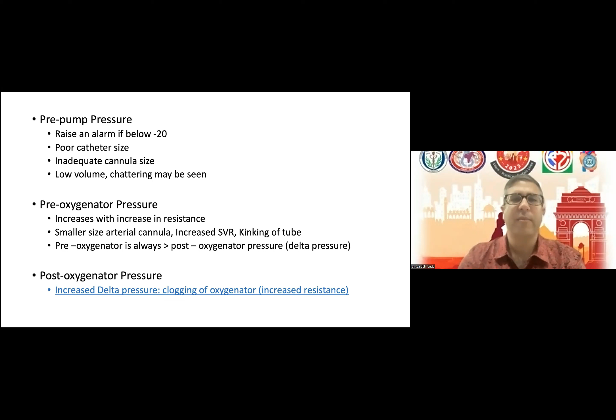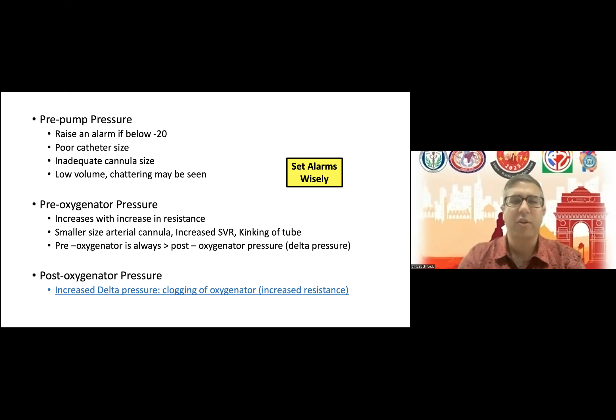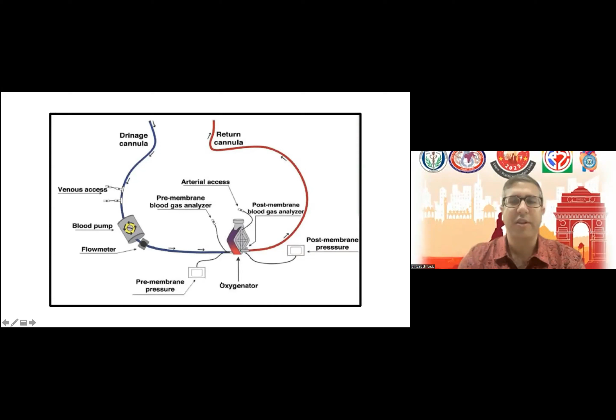There are no fixed values of pre-oxygenator and post-oxygenator pressure. But the difference between the pre and the post is called the delta pressure. And if the delta pressure increases, that means there is increased resistance in the oxygenator, and most probably there is clogging of the oxygenator and some clots can be there. We should set alarms wisely. We should monitor the patient, see what the normal pressures are that the patient is keeping, and then set alarms. So this is a common circuit in which we can see this is a drainage cannula. This is the pre-pump pressure, this is the pre-oxygenator pressure, and the post-oxygenator pressure, and the difference is the delta pressure.